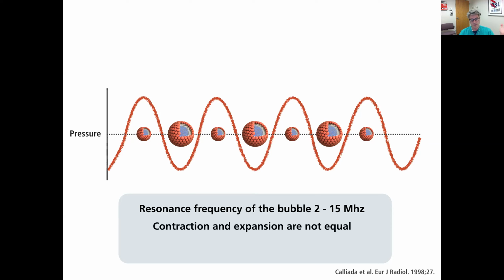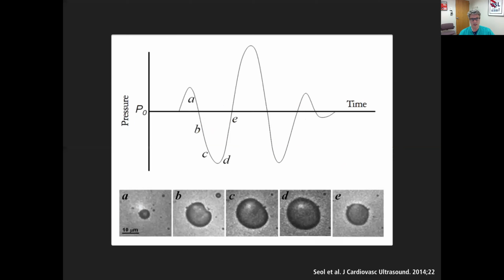One key principle to know about these bubbles is that the contraction and expansion are not equal, which leads to non-linear behavior, which can be used to detect the bubbles later. So I would remember that. And this whole principle of oscillation enhances the echogenicity by a factor of 1,000, compared to just looking at the impedance difference. But the oscillation is really what makes them so easily detectable.